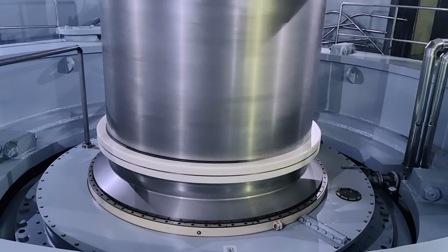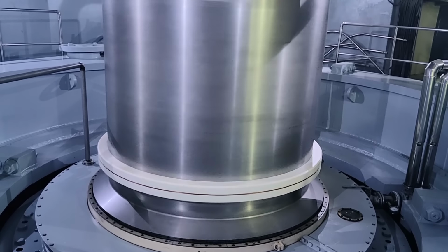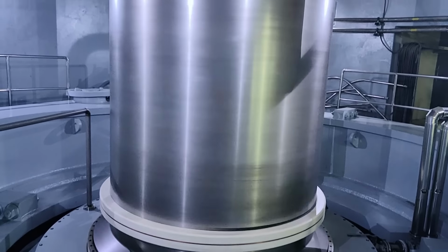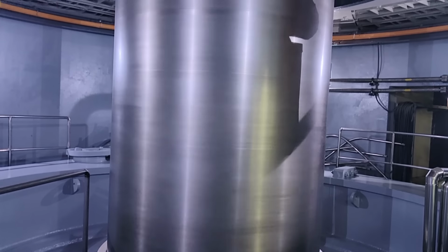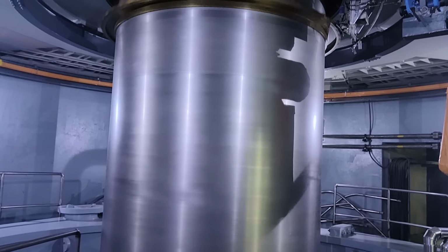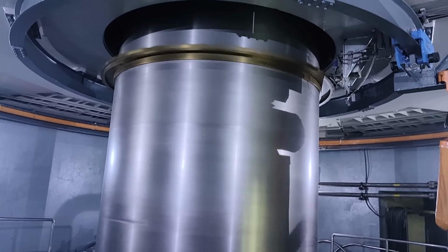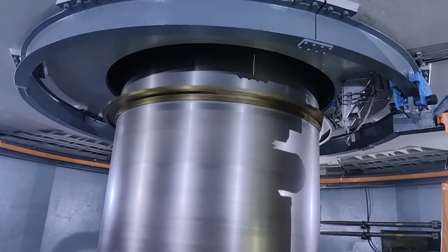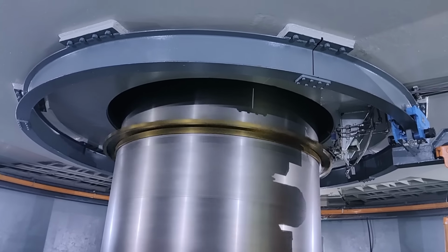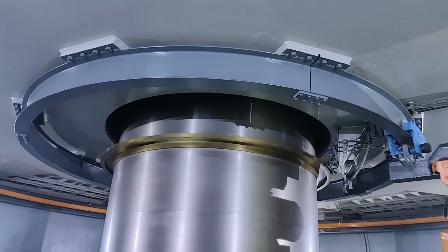What you just saw is the only protection of this power plant against water hammer effect in case of any emergency. This pressure releasing valve opens only 20% during the startup sequence for just a few seconds, and if this valve does not open during the startup sequence, the unit startup does not proceed further.